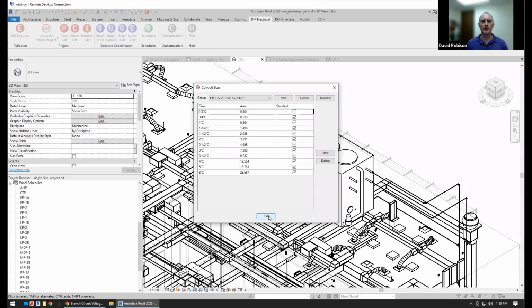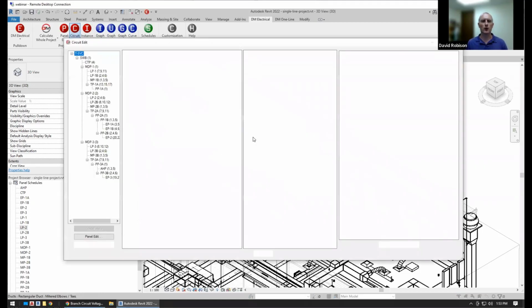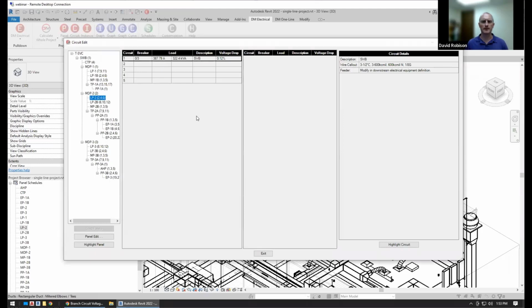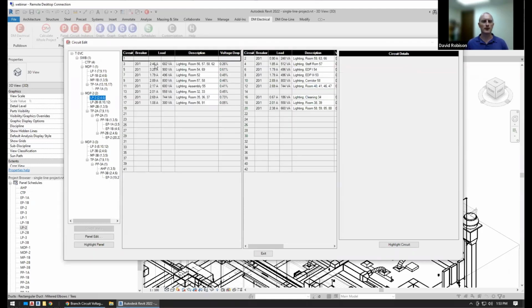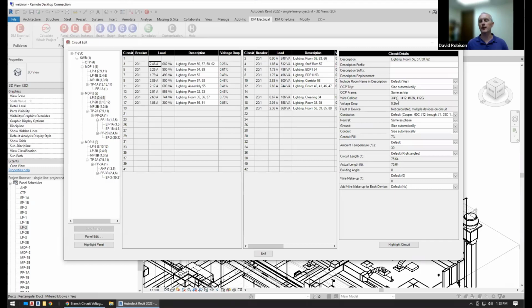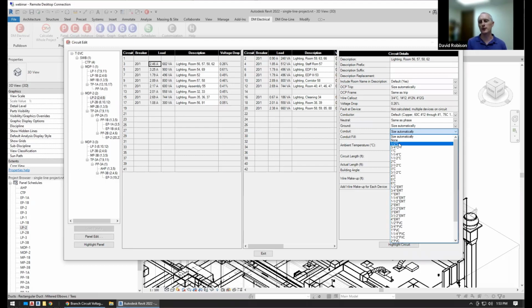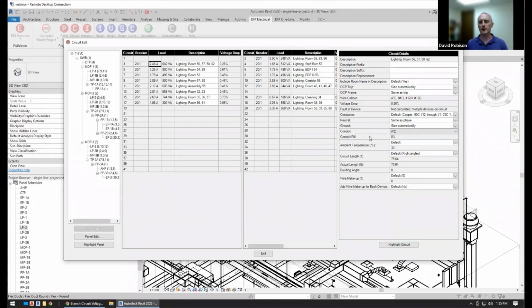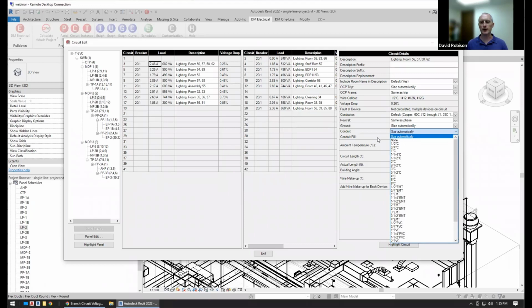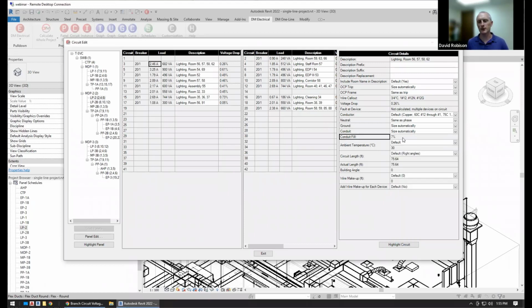You can still choose it as an option if you want to, but the software is not going to choose it as a size. So if we uncheck that, go back to our circuit edit command and take a look at this here. Now we have a 3/4-inch conduit rather than the 1/2-inch, but we still have the option to choose the 1/2-inch conduit if we want to for a specific circuit. If you do adjust your conduit, it will recalculate that fill for you. 1/2-inch is 13%, and then the 3/4 is 7%. So it will display that value. So if you are changing your conduit, you'll see what it is.